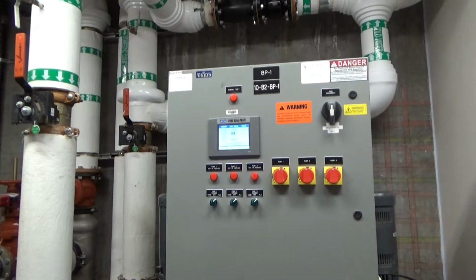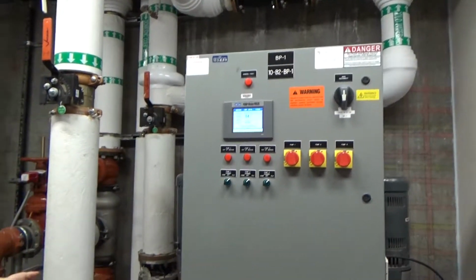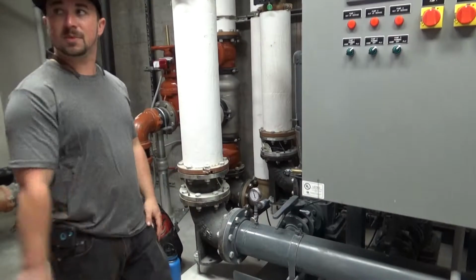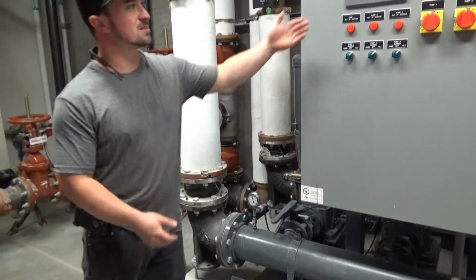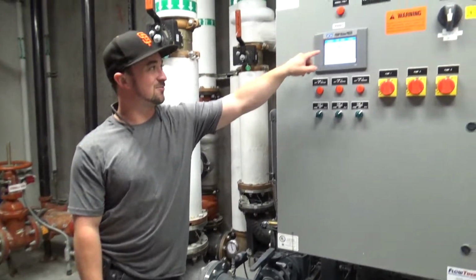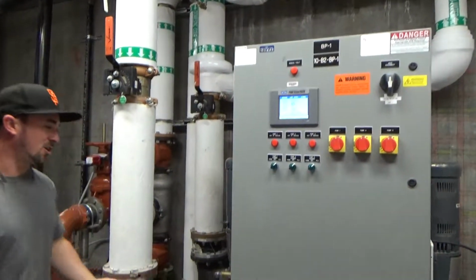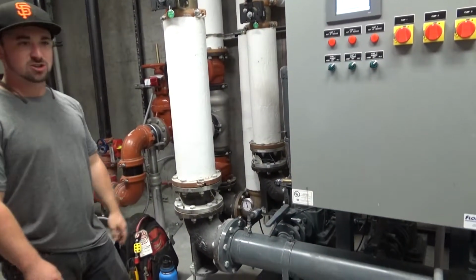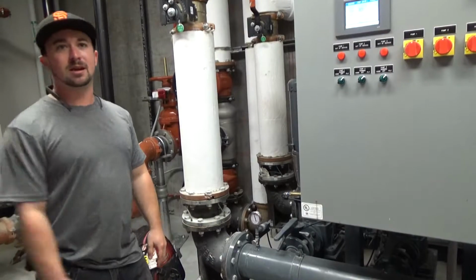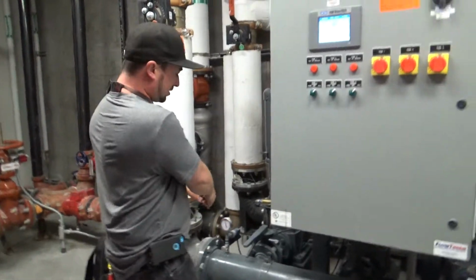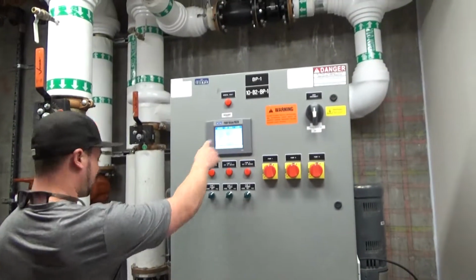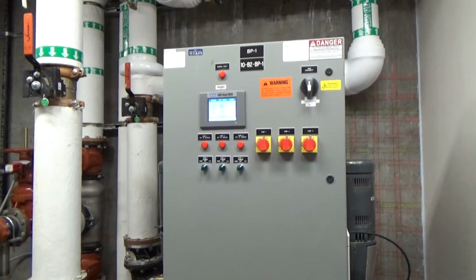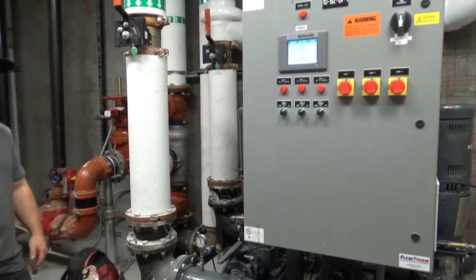So pretty much you're checking that the transducer is reading correctly by using the gauge to check it. It's kind of hard in this scenario because everything is 85. Suction's 85, discharge is 85, set point's 85. But say the discharge pressure you had in the building was 125, then you would be able to look at that gauge: okay, this says 125, that says 125. Transducer's working correctly and everything's operating per specification.